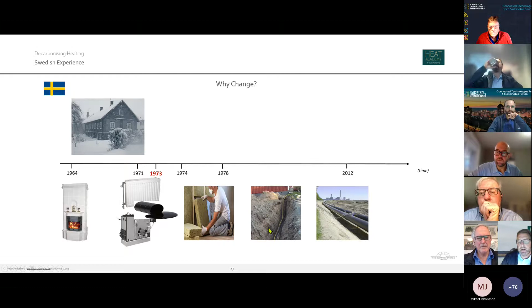As I referred to before, this house where I grew up was connected first to a small boiler using biofuels, and later to a large regional heat network. It followed a process that's important background for discussing industrial waste heat sources. First, we reduced the demand for heat in these buildings, which was critical. The more we reduce heat demand, the better off we are in terms of capex, we can reduce pipe sizes, and get less losses in the system when operating it, reducing operational cost.